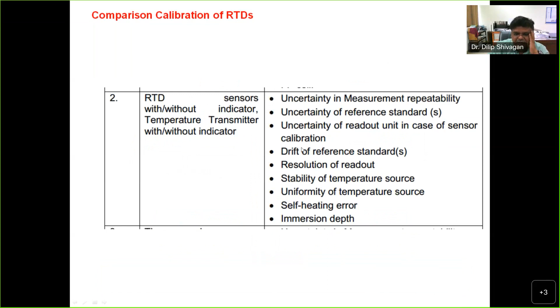So there are also, as I said, specific criteria. They have given very categorically what level of uncertainties, and what parameters need to be taken into account for the measurement. So as I said, if you have the range say minus 50 to 400, if you measure more number of points, your dispersion within the points will be very, very less. So deviation and uncertainties will be attributed very, very accurately, so that the table that is generated between these points will be quite accurate. So you may have a sensor range which is very wide, but if your application is for a typical range, we suggest you measure more number of points in that typical useful range, so that you get very less correction and uncertainties.